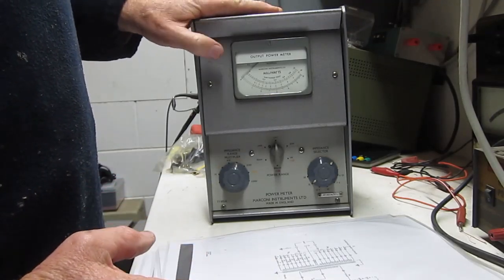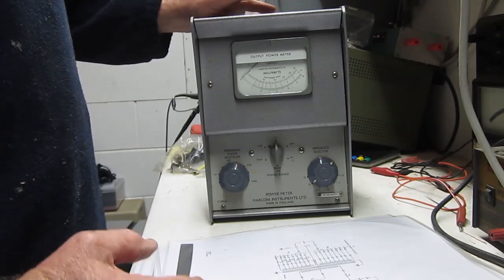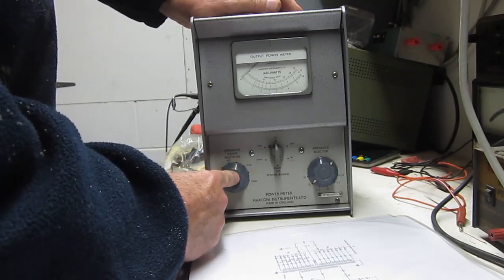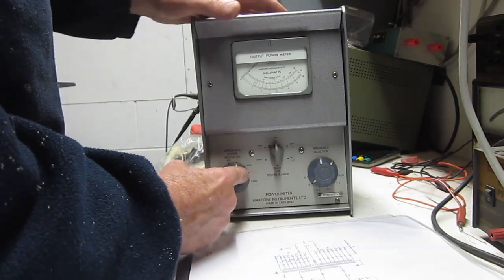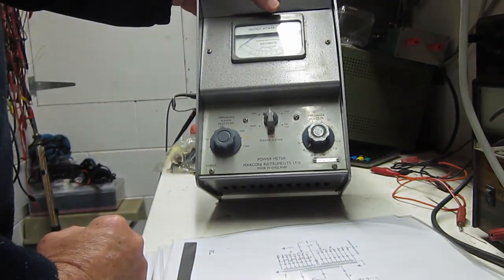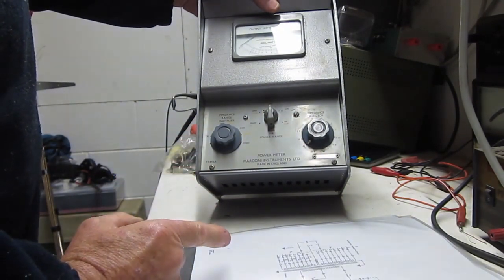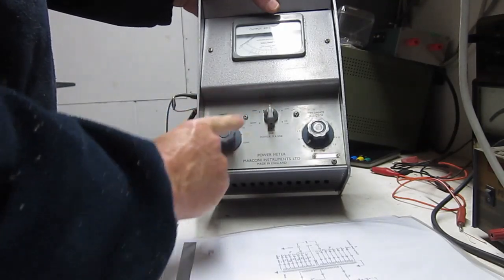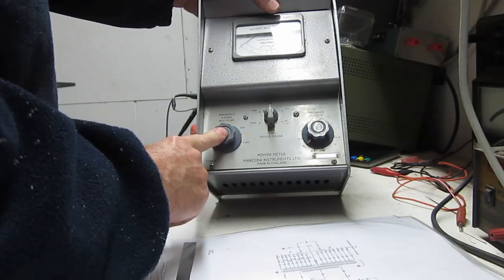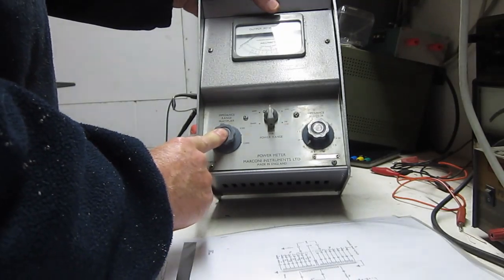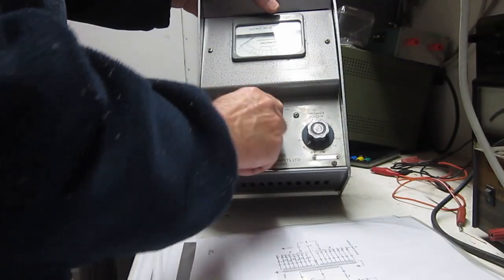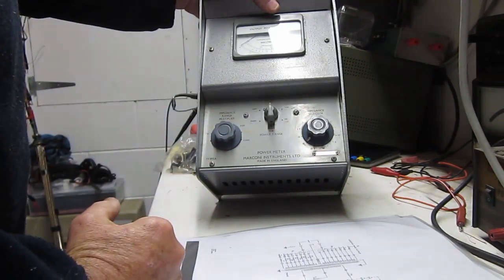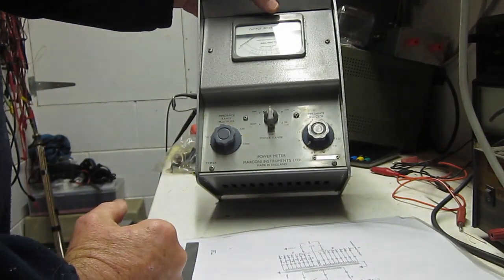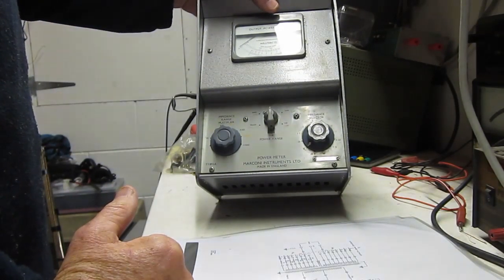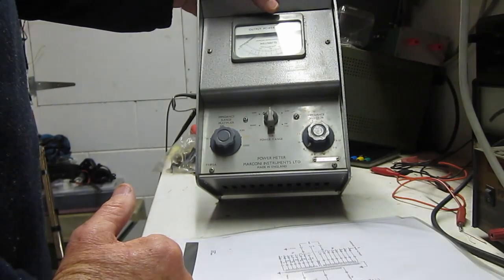The entire instrument is resistive, so the multiplier and impedance selection are tappings from the transformer, or a combination of tappings from the transformer and resistive elements inside the instrument. Even the power range selection is again completely resistive. The instrument uses a diode bridge to actually measure and deliver energy to the meter circuit.